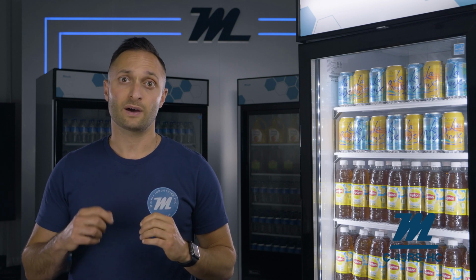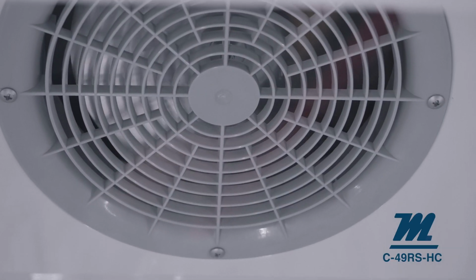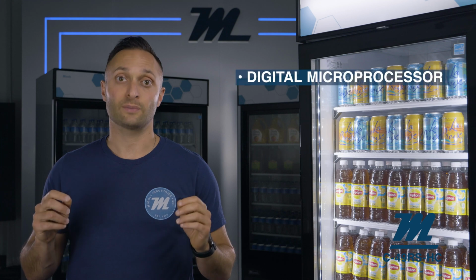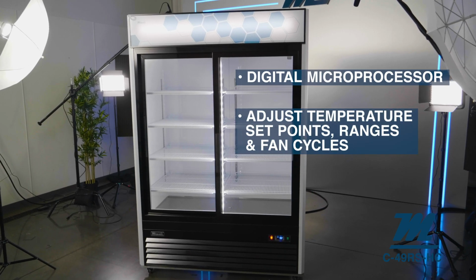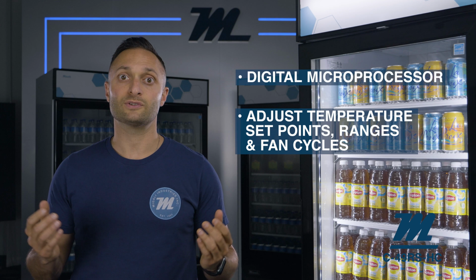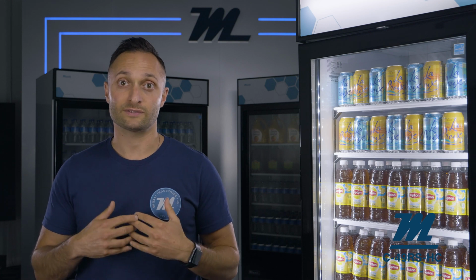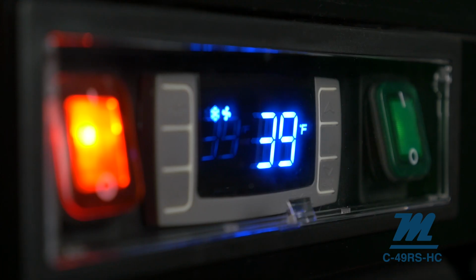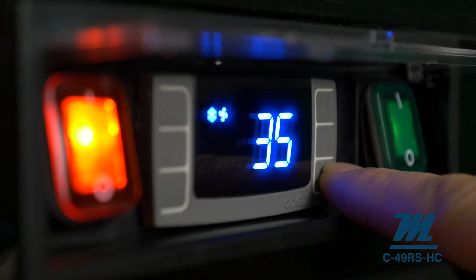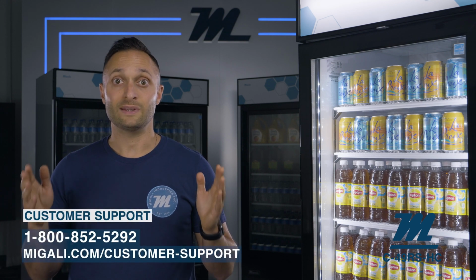All C-Series models are designed with a forced air refrigeration system, which simply means warm air is forced over the evaporator coil, heat is absorbed by the refrigerant, and cold air is circulated down the back wall and through the interior. This Migali model is operated by a digital microprocessor thermostat. The digital microprocessor reduces energy consumption and controls when the compressor turns on and off, fan and defrost cycles, door lights, and enables the user to operate this unit at specific temperature ranges. The LCD microprocessor keyboard is conveniently located on the top right corner of the bottom ventilation grill, and temperature set points and ranges are easily set in seconds. Refrigerators are factory preset to operate at 33 to 40 degrees Fahrenheit. However, you can easily adjust the temperature range if needed. Just remember to call our tech support department if you need any help with this.